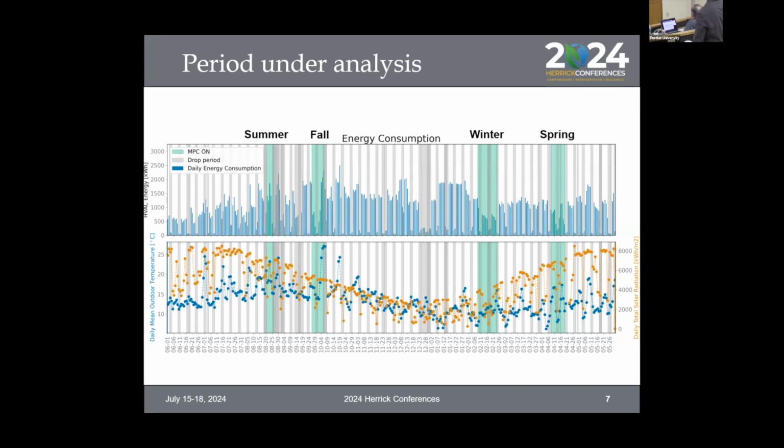No, the drop periods are mostly weekends and holidays because the system goes on a schedule and the building is unoccupied and the HVAC is not working on the weekend. So we felt like those were not meaningful data. And then there is a bigger period in December, and that was a problem of the LC system where we didn't get any monitor data, so we didn't consider it.